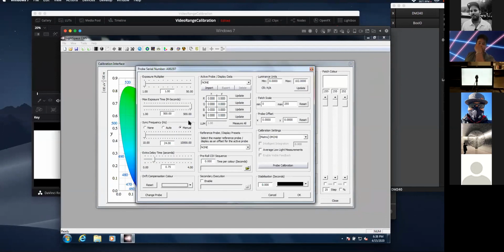The CR100, for those of you that have that, has a few different sync options. You can do an auto sync, a manual sync, or no sync. Don't do no sync, it will fail on you. For auto sync, what it will do is before it takes a reading, it will actually measure the frequency response of the display, and then it will take the reading. And it will do that before every single reading. That slows down your calibration time a lot, so it's better to use a manual setting.